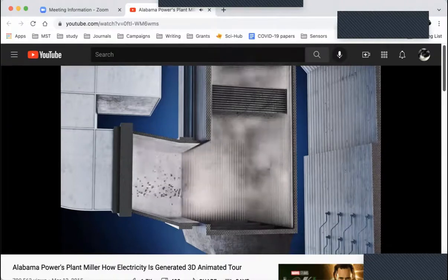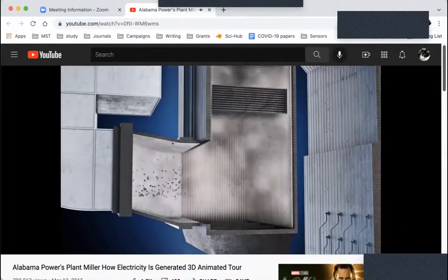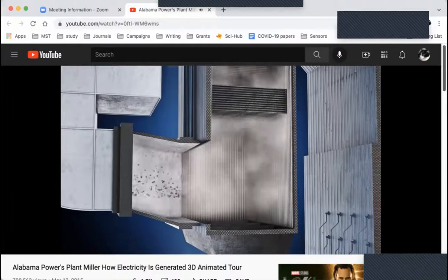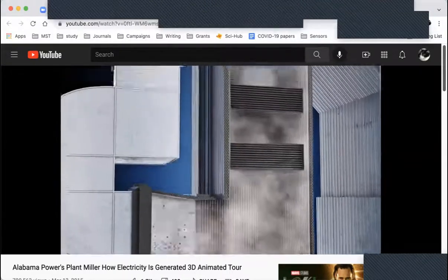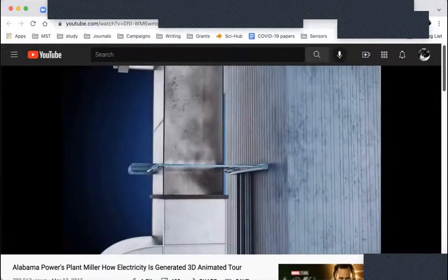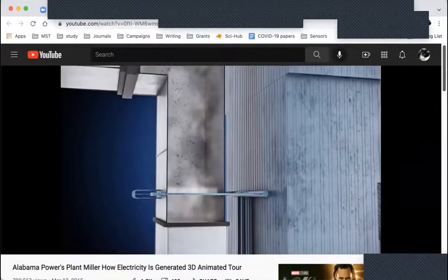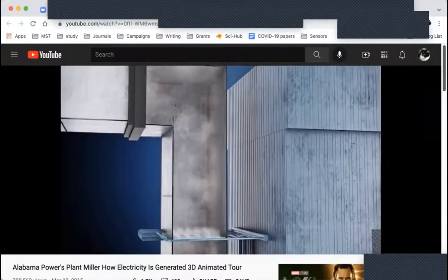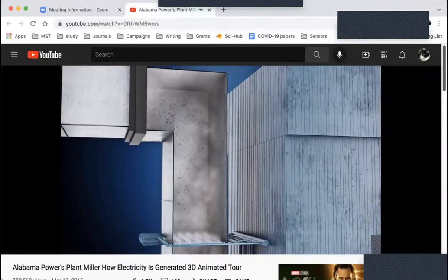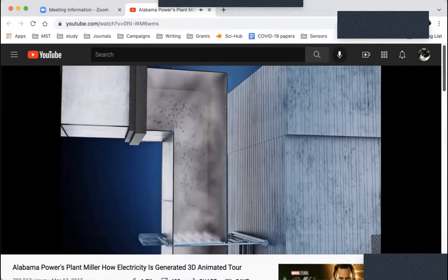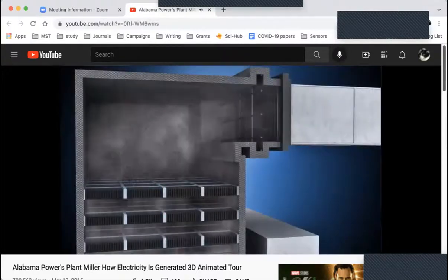This economizer ash is pulled by vacuum, mixed and sluiced with water to the ash booster station where it is moved to on-site storage. Flue gas, a byproduct of combustion, exits the boiler and enters the selective catalytic reducer, or SCR. While entering the SCR, ammonia is injected into the flue gas stream, where it reacts with several catalyst layers to reduce the nitrogen oxide compounds.